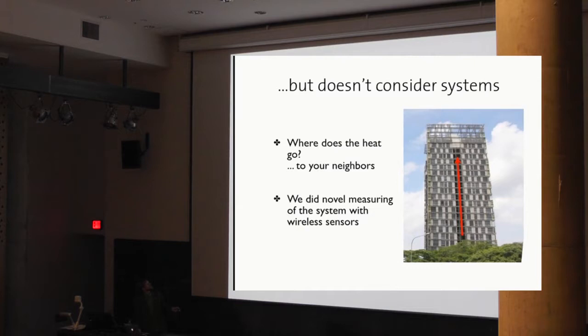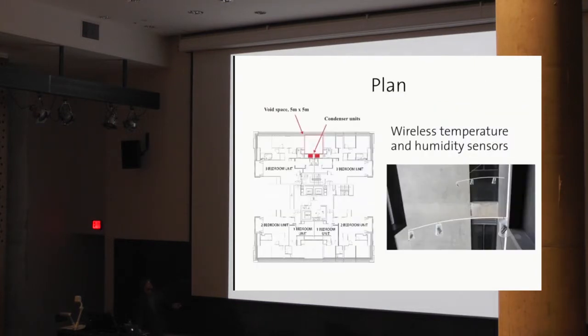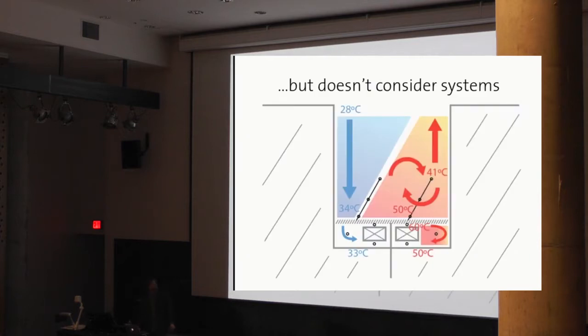But it doesn't consider this effect - all the heat is going up to your neighbors. So we installed sensors in these cavities and measured the temperature profile. The most fascinating thing we found was not only a significant stack effect, with 10 degree higher temperatures at the top of the building, but on top of that, the louvers actually increased the air temperature of the split units on this side of the building by another 10 degrees.